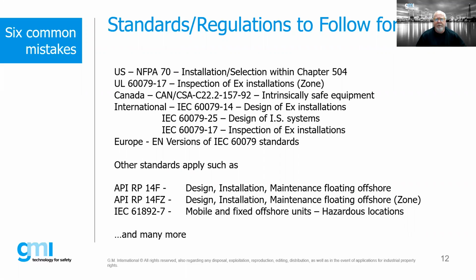So what we follow as far as standards are concerned is important to understand, because depending on where we are in the world, we have to follow whatever particular wiring regulation standard. Again, in the United States, we follow the National Electric Code, the NFPA 70. Chapter 504 is all the information for the installation and design of IS systems. We also have a UL standard that's just recently been published for inspections of EX installations, for zone installations. In Canada, there's a couple different documents, but the CAN/CSA is your intrinsically safe systems document.